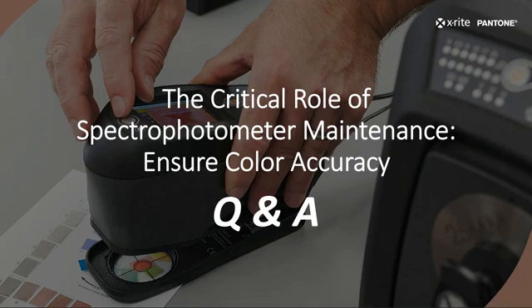So the key is this, right? You could use a different tile set with every single device because all those tile sets have one thing in common. They were measured with an X-Rite centroid device, likely the exact same X-Rite centroid device, right? And so the values for the tiles, while the tiles are different and their values are going to be different, were all measured with the same device. So when you send those tile sets out to, let's say you have 10 different locations, those 10 instruments measure those tiles. What's going to happen is those instruments are each going to be profiled to match back to that same centroid device that measured all those different tile sets. So it ties them all immediately back to each other.